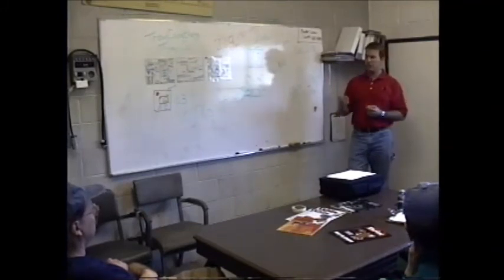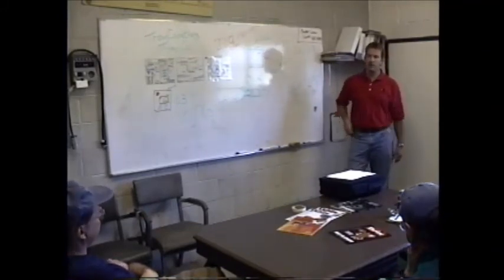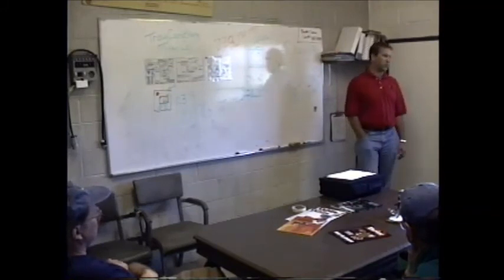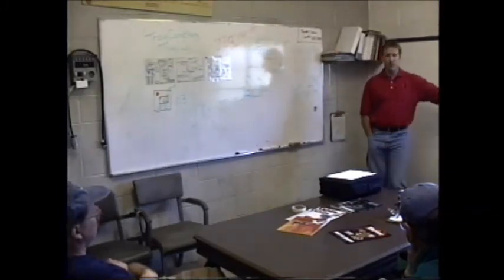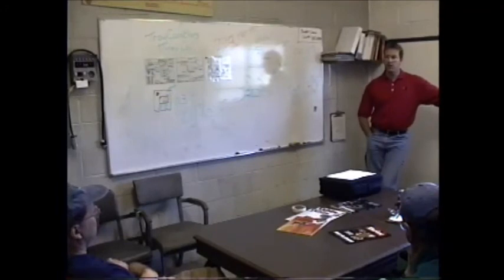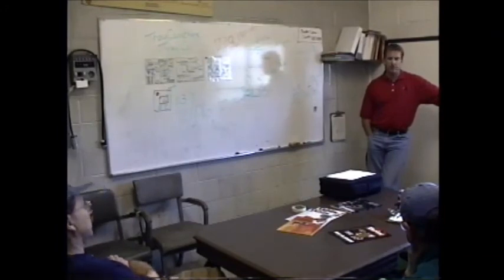So the smallest percentage we can set it at for these deep-seated fires, down to 0.1 or 0.2%, is going to give you a much better soaking liquid than if you try to go with more and more foam concentrate. And if you can avoid any aeration, it'll just slither through and soak into that material and hopefully penetrate down into the heat and start to smother out the fire. But that's just one little tidbit of information.